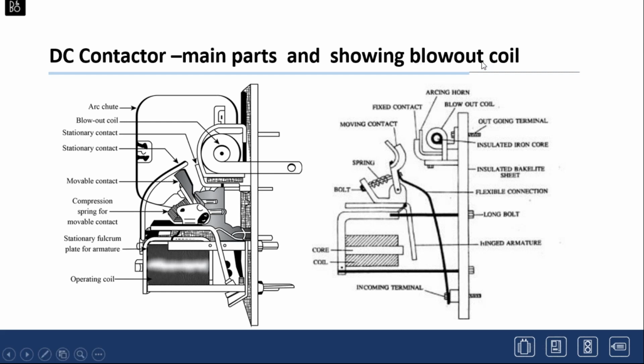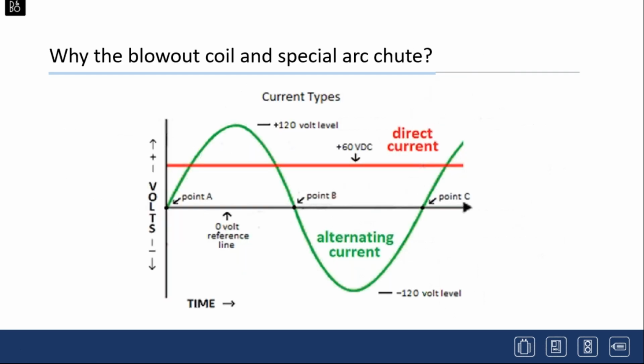One of the reasons I wanted to pull this up is that we talked about the blowout coil, and that's another question that we frequently get: what's a blowout coil, and why the difference in a blowout coil on an AC and DC device. On an AC power circuit, you have a 60 cycle wave here, and you have 3 points during this cycle, point A, point B, and point C, when the voltage is actually 0. So it becomes relatively easy to interrupt the arc because the line voltage is going to 0 60 times a second. So it's relatively easier to interrupt the alternating current than it is direct current.